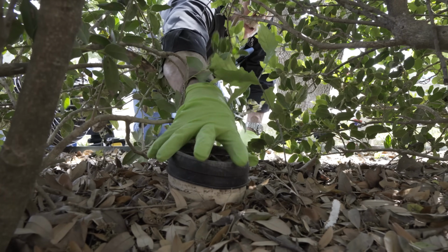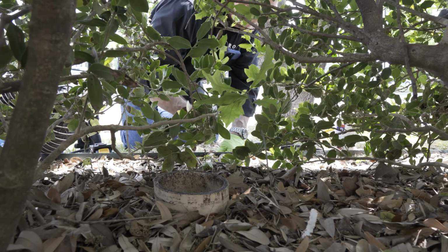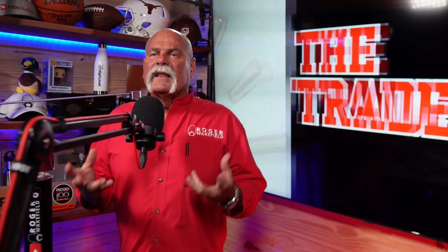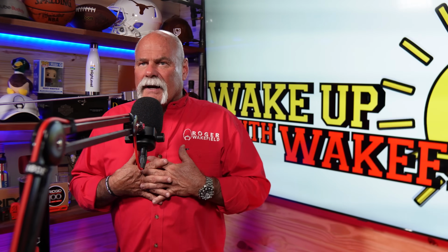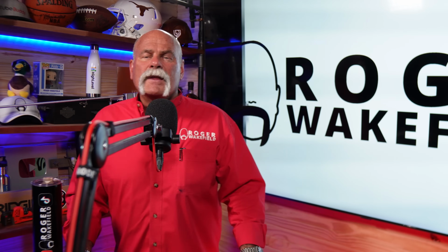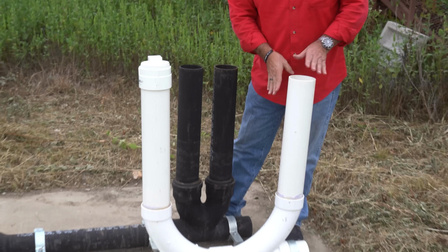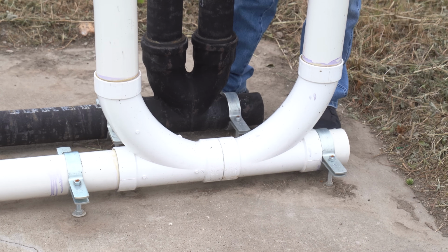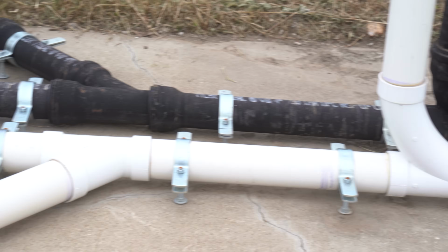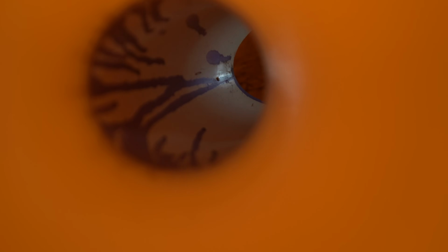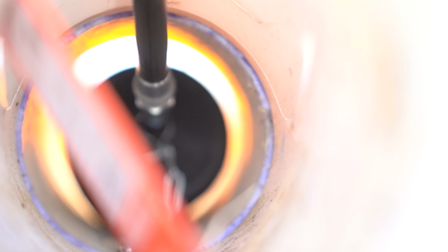Number 7, no cleanouts for drains. Not providing cleanouts in the plumbing system can make maintenance and clearing clogs much harder than it needs to be. Lack of cleanouts is a tough one. We specialized in slab leaks, leak detection, sewer isolation, things like that. You have to have a good double cleanout, a double combo cleanout in order to test that right. You need to be able to put a test ball right between them. You need to be able to look on the other side and make sure it's not leaking. And that way, when you fill it up, you know everything on the other side is good to go.